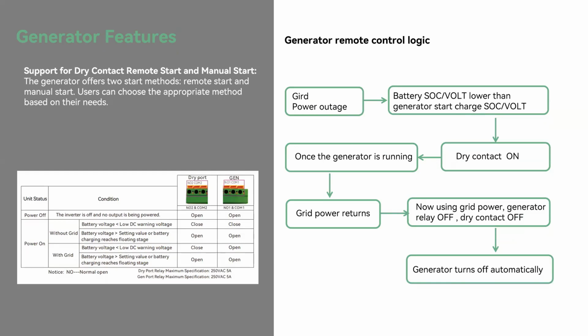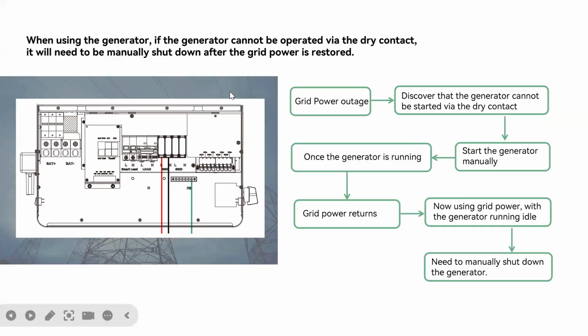As for the manual start, for example when the generator cannot be operated remotely through the dry contact ports, we have to manually turn on the generator when there is a grid power outage, and when the grid power is back, we have to manually shut down the generator.